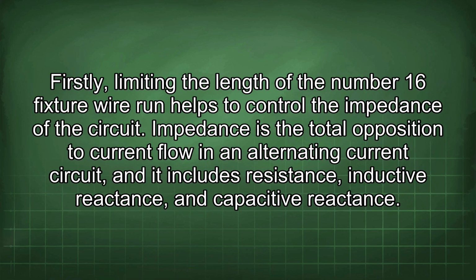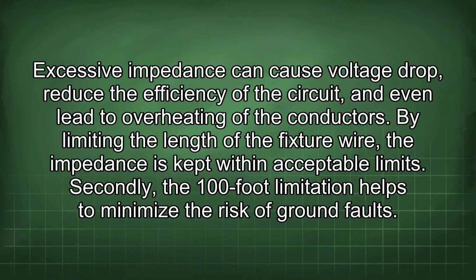Firstly, limiting the length of the number 16 fixture wire run helps to control the impedance of the circuit. Impedance is the total opposition to current flow in an alternating current circuit, and it includes resistance, inductive reactance, and capacitive reactance. Excessive impedance can cause voltage drop, reduce the efficiency of the circuit, and even lead to overheating of the conductors. By limiting the length of the fixture wire, the impedance is kept within acceptable limits.